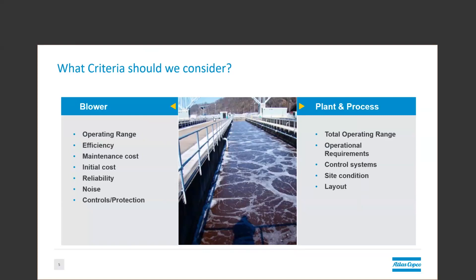You also shouldn't put a blower that has limited start-stops in a process that turns on and off more than three times a day, for example. Control systems for the blower, whether integral or remote, run in conjunction with control systems for the plant. Is the plant controlled with speed, pressure, flow, or other process variables, such as DO or ORP?